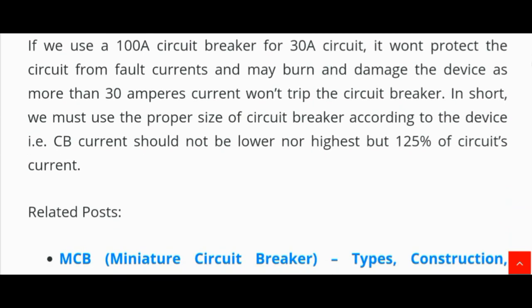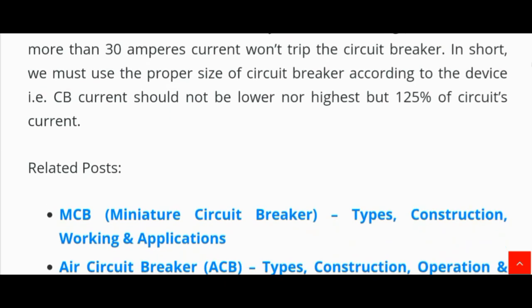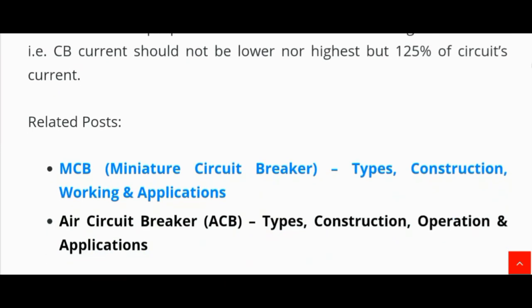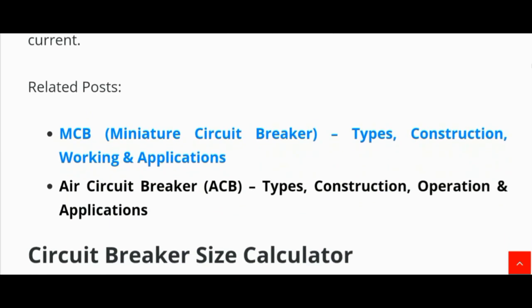For example, if we use a 100 ampere circuit breaker for a 30 ampere circuit, it won't protect the circuit from fault currents and may burn and damage the device, as more than 30 ampere current won't trip the circuit breaker. In short, we must use the proper size of circuit breaker according to the device — the circuit breaker should not be lower nor higher, but 125 percent of the circuit current.